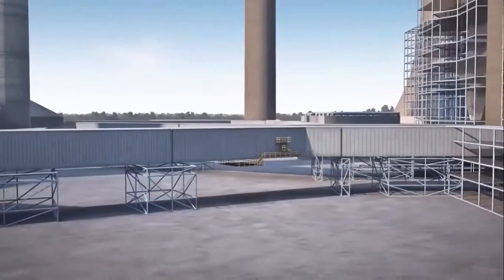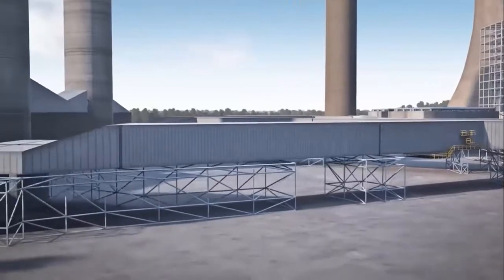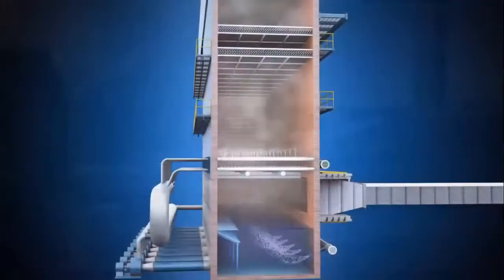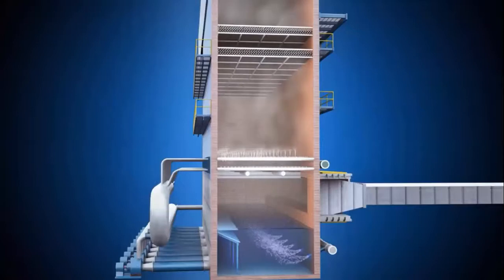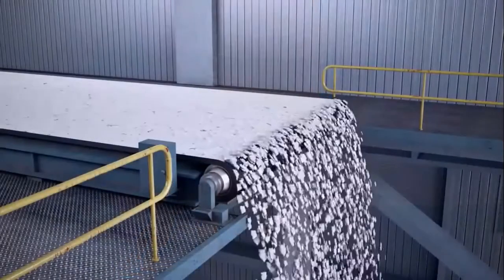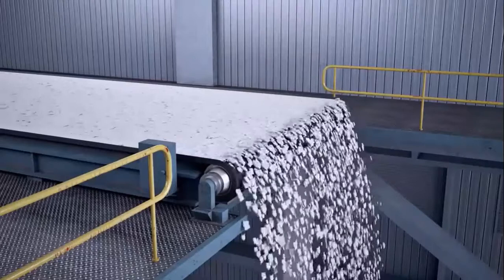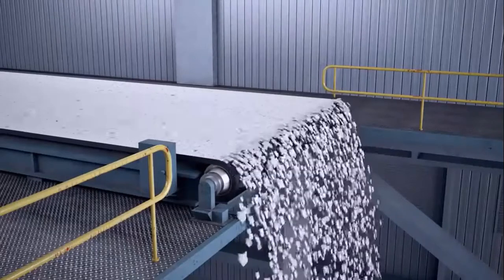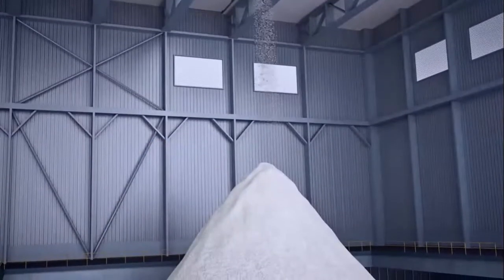The flue gas then passes through the induced draft fans and to the scrubber, where booster fans pull the flue gas from the plant and push it through the scrubber absorber. In the absorber, flue gas mixes with water and limestone. The limestone reacts with and removes about 98% of sulfur dioxide, creating the byproduct of gypsum. The wet flue gas exits out the top of the absorber through to the wet stack, and a gypsum slurry stream is pulled from the bottom of the absorber and sent through a dewatering facility. Inside the dewatering facility, most of the moisture is removed from the gypsum so it can be sold for use in wallboard.